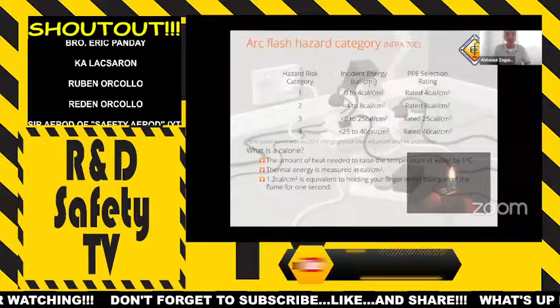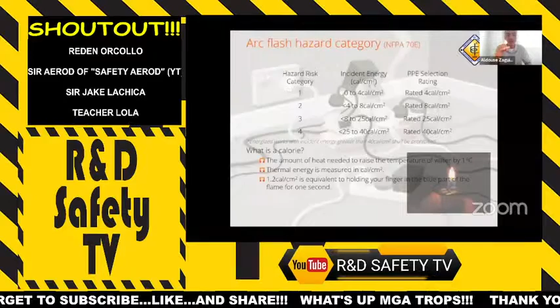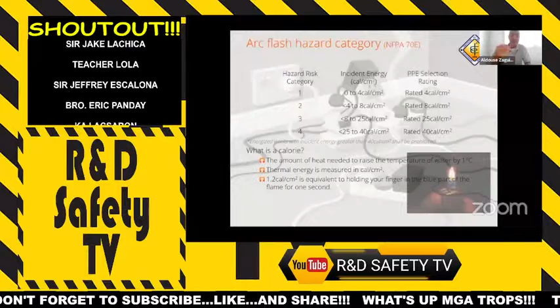Because going beyond category 4, even if those PPEs are available, it is still very fatal, and the assurance of really protecting the person is not that high. It's too low. There's really not much confidence that the person can still be protected beyond 40. Okay? But if you really have no choice, you really have to contact the qualified persons to make the evaluation and the assessment, put up the program, decide how we are going to approach the job, and how we are going to protect our personnel. But again, let me repeat, we only recommend that you look up to category 4. Okay? Beyond that, it's going to be really very dangerous.